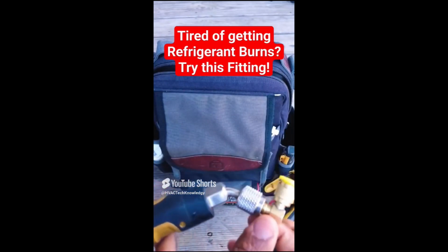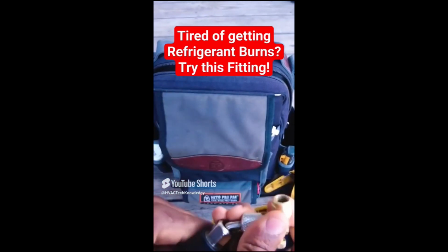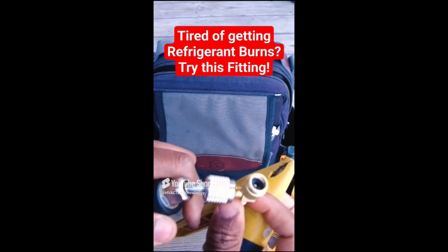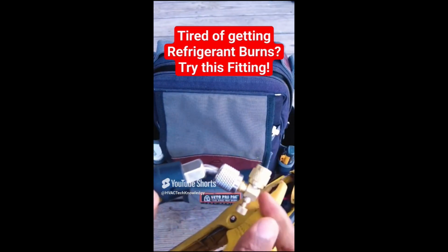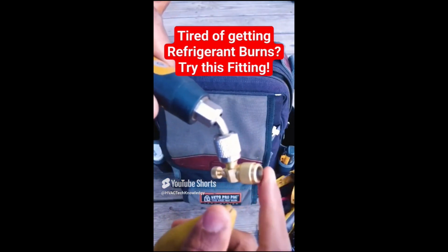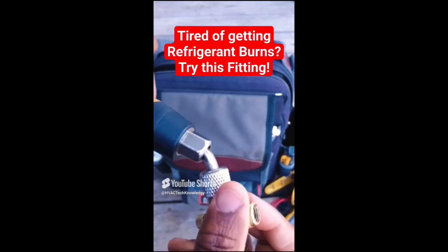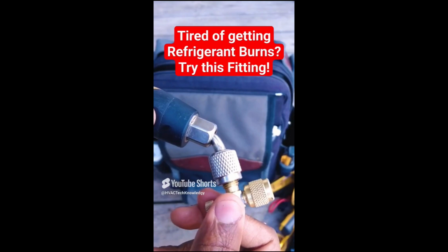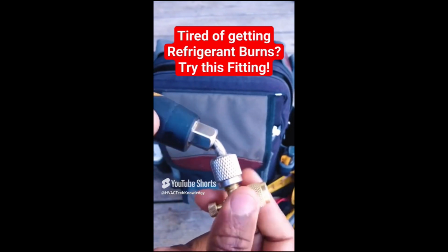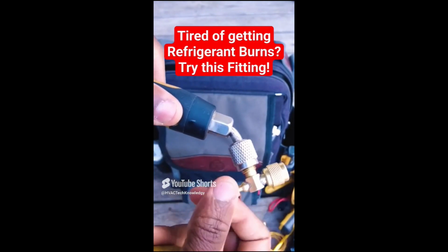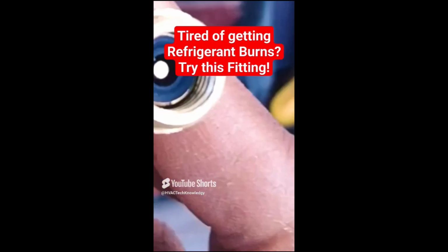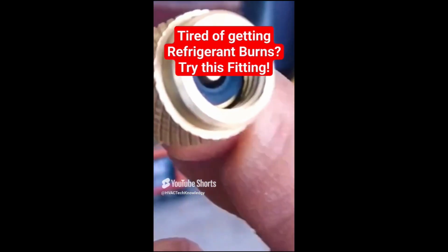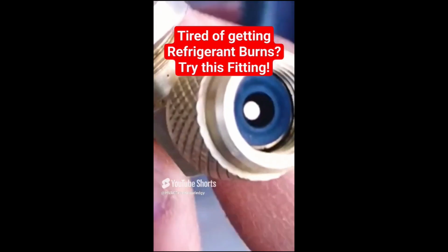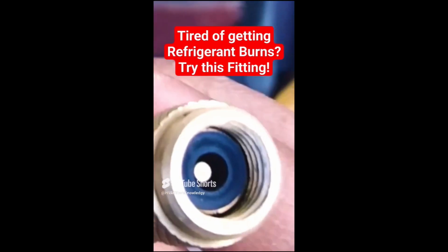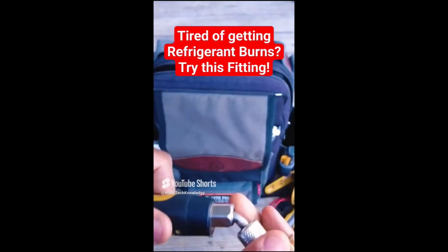So this is just a little thumb screw adapter here, and what it does is it allows you to put the pressure transducer on without actually depressing the Schrader core valve. So you can screw it on without depressing it and shooting liquid out. Once it's sealed, you turn this thumb screw in like this, and you can see it protrudes out, or screw it out and it recesses in behind the gasket. That's how it works - I like it, it's okay.